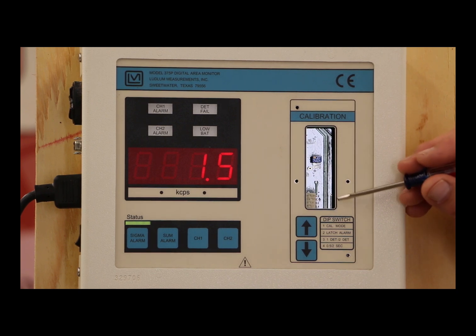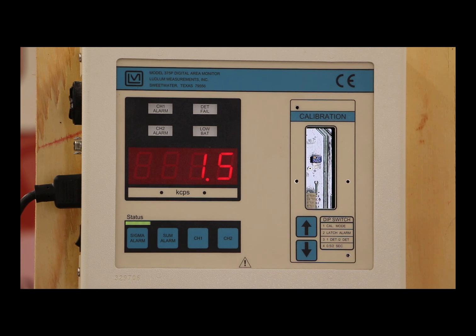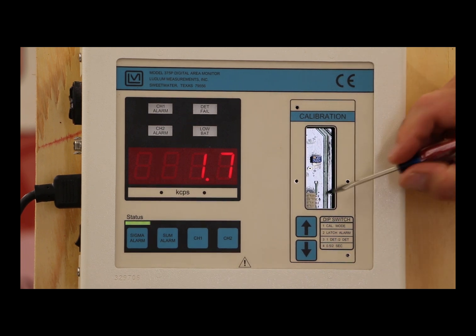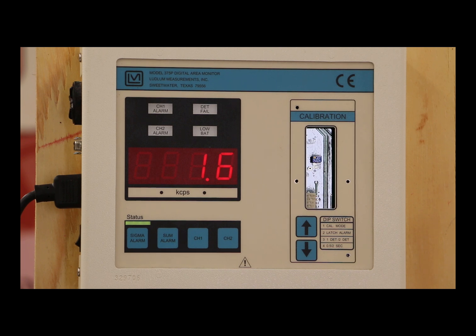We have a few other dip switches here. The second one is latching alarm. What happens when you get an alarm, does it latch? Latch means that it stays on until someone comes and touches one of these buttons and acknowledges it. Currently, as you saw earlier, when we get an alarm and I move the source away, the alarm goes off. It's in the non-latch mode. That's with the dip switch number two all the way to the left. If I moved it to the right, it would alarm until someone came and pushed either the sum button or the sigma button.